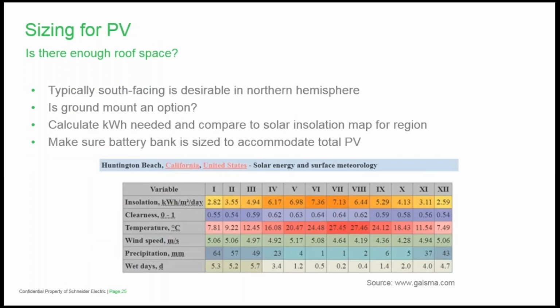So sizing for PV, that can have a lot of different variables. It could stem from, maybe you have limited roof space. If you have ground mount, that's not going to be an issue, but typically you want a south-facing array if you're in the northern hemisphere, if you can help it. That's not always possible with different facing angles of roof space. And then, of course, if you do have different angles, you're going to need to make sure that you're not running a single controller using different facing strings, because that's not going to be very efficient. You might want to look at microinverters AC coupled for something like that, or module level power electronics that use optimizers.